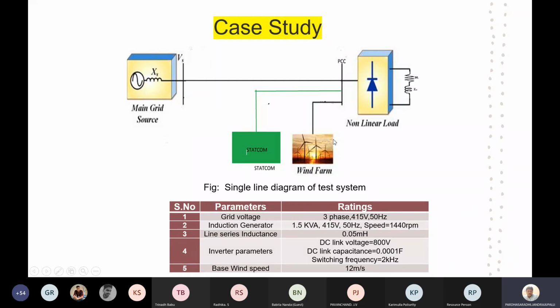Whenever the wind farm and the nonlinear load are connected, the impact is on the main power source. That's what I said to you. The harmonics which are produced by the load, or injected in the load, are not meant for the load itself. They are again supplied to the source side, our grid side. So due to the presence of the load, these harmonics will be produced on the grid.